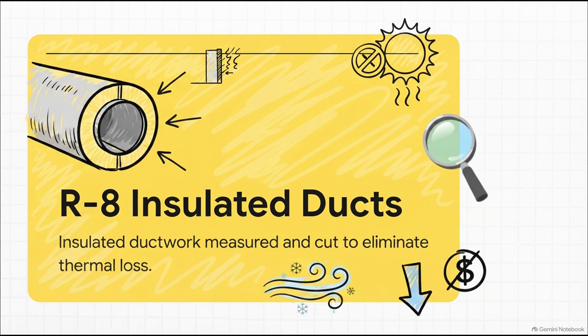Once the math is completely dialed in, the materials matter just as much. We exclusively use high-grade R8 insulated ductwork for every single run—a very thick, highly thermally resistant material. Why does this matter so much? Because running uninsulated or poorly insulated ducts through a blazing hot floor to attic essentially guarantees massive thermal loss, which directly drives up your energy bills. R8 insulation totally prevents that, ensuring the air stays crisp and cold as it travels to your vents.